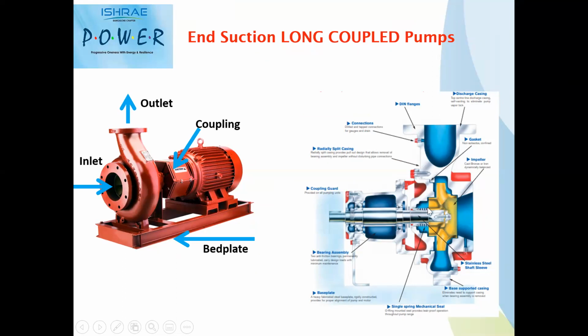This is the discharge. The impeller is mounted on a cantilever design pump shaft where you have a bearing assembly. The pump shaft is supported by inboard and outboard bearings. Two bearings are used in any end suction, long coupled pump. There will be a mechanical seal arrangement here, which prevents leakage from the pump casing and shaft. This is the impeller. This is the eye of the impeller, where water enters from one side of the impeller and will be discharged to the top side of the pump. So this is a typical end suction pump, and it is called long coupled design because it has a separate coupling here, and the pump shaft and motor shaft are coupled through a flexible spacer type long coupling, and this pump is mounted on a base plate.